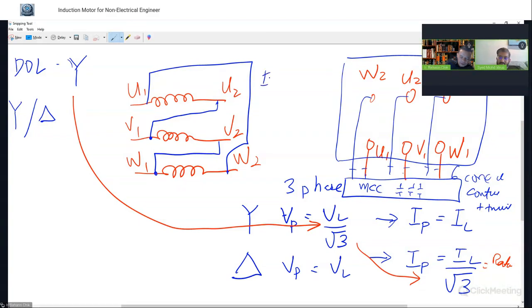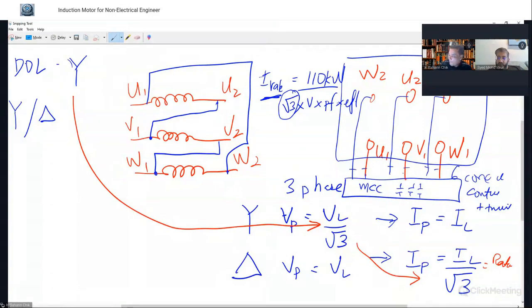For example, if the motor is 110 kilowatt, then you divide by square root 3, then you multiply by the voltage, then you multiply by the power factor and efficiency. So this is the rated current. If you see this over here, regardless of whether you are connecting star or delta, this factor square root 3 is there. So regardless of whether you are connected in star or delta, the rated current is the same. Alright. And then continue on the question.